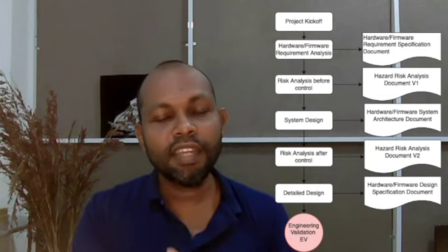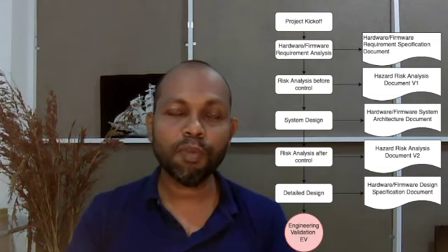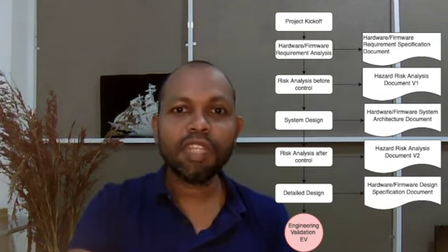So that's why we say we have to do a new system design based on the new system risk analysis, and then go for a new risk analysis after the controls. So there's a risk analysis before the controls. If one or two risk items might be too high, then you have to go for system analysis, including those risk analysis, risk mitigation steps, and then go for a new risk analysis. After the new risk analysis, we can go for a new system design where all these risks are mitigated up to an appropriate or acceptable level, and now the device is ready for the development phase.